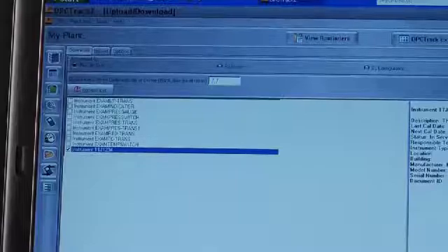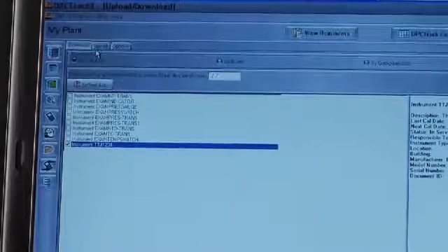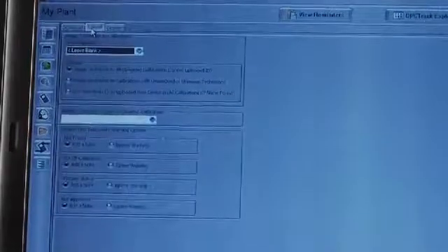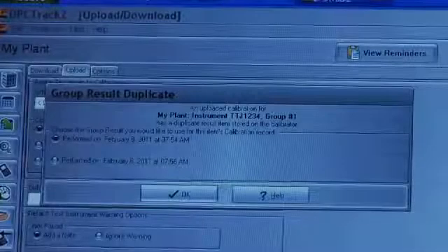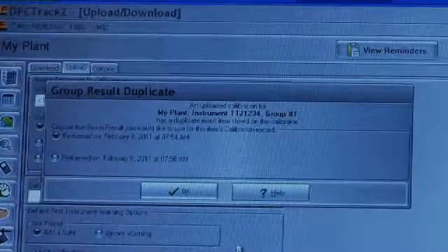Next we're going to upload the as-found calibration result in the calibrator to DPC Track 2 software. Select upload, confirm settings, then initiate upload from the calibrator to the software. Confirm upload settings.